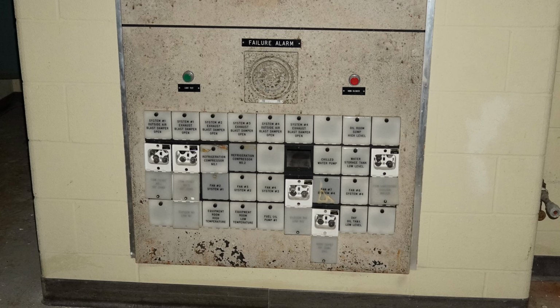We have a lot of blast dampener alarm indicators, fan system control indicators, equipment room temp high and low, oil tank low and high, water storage high and low, refrigerant high and low, plus a lot of blast doors, blast dampeners, and controller indicators in here as well. So this is definitely a hardened bunker designed to take a hit, and this is proof of that.